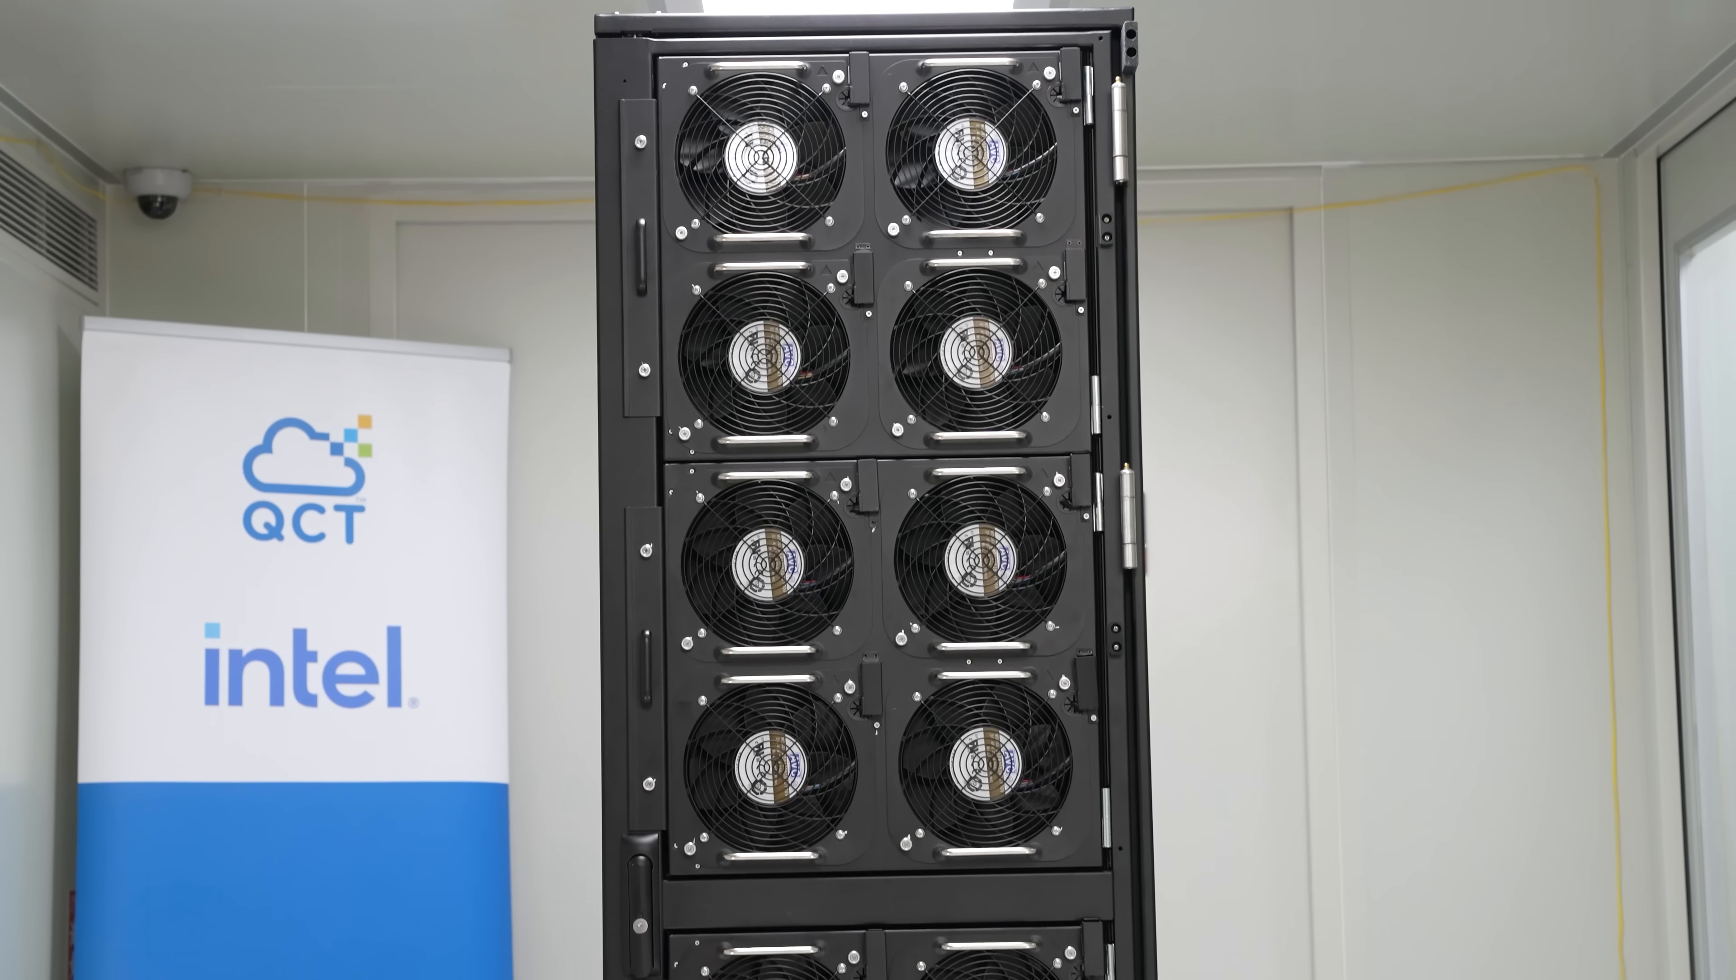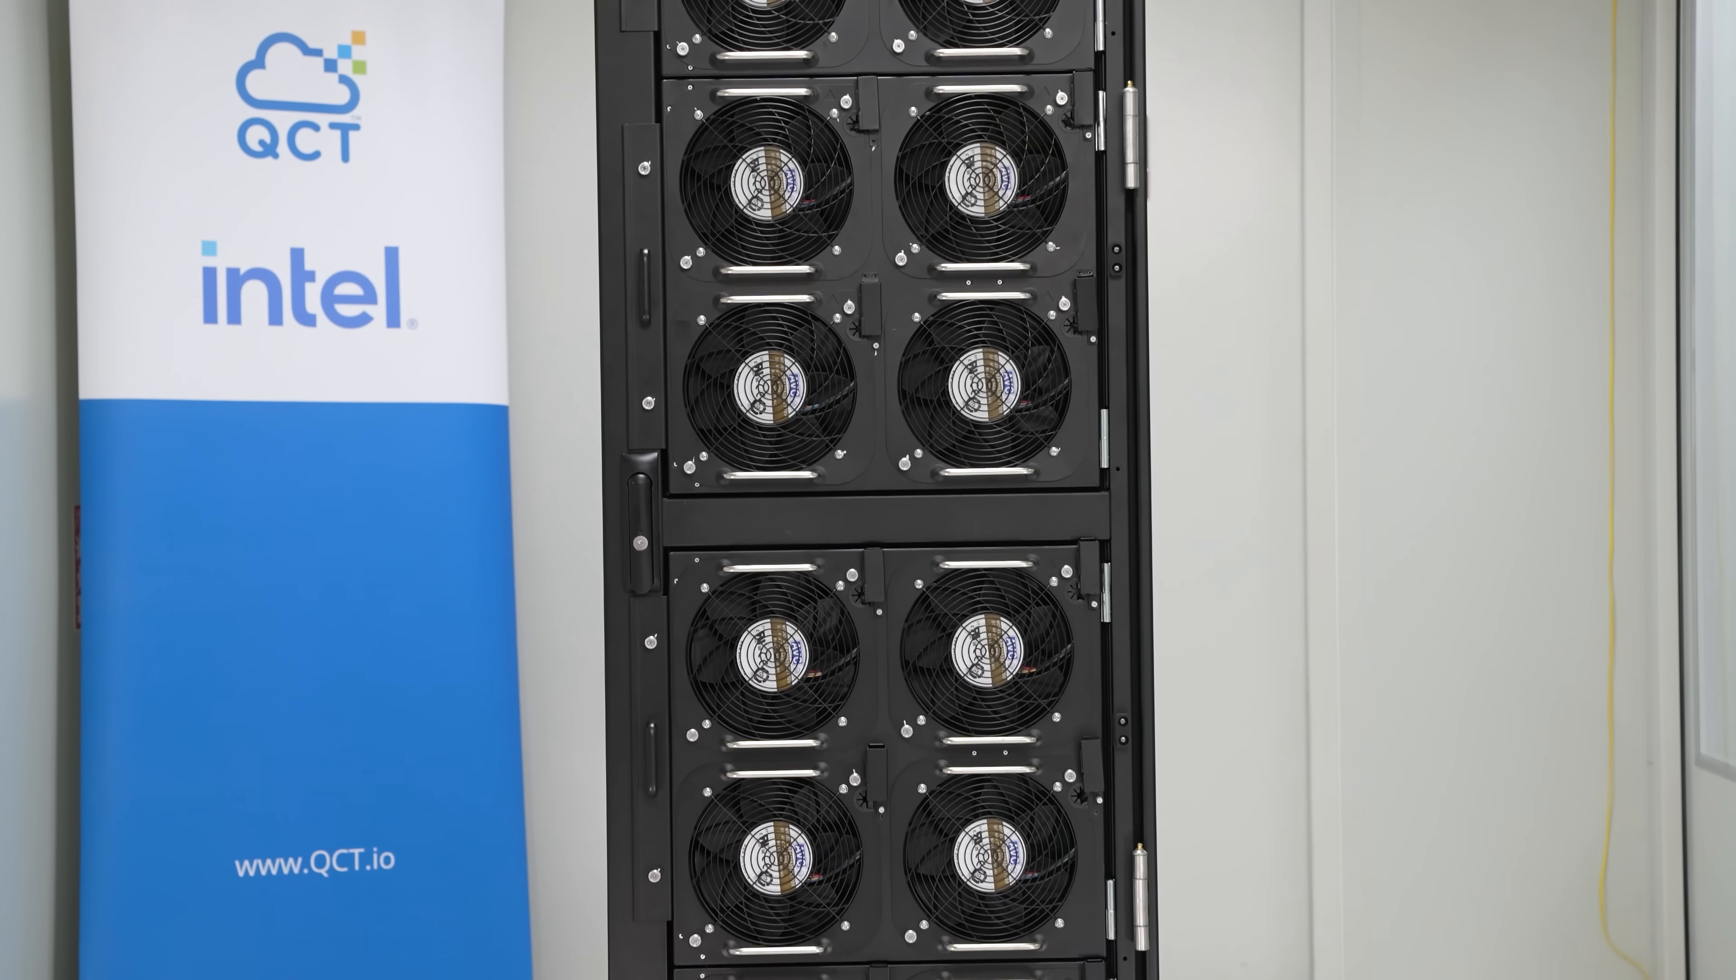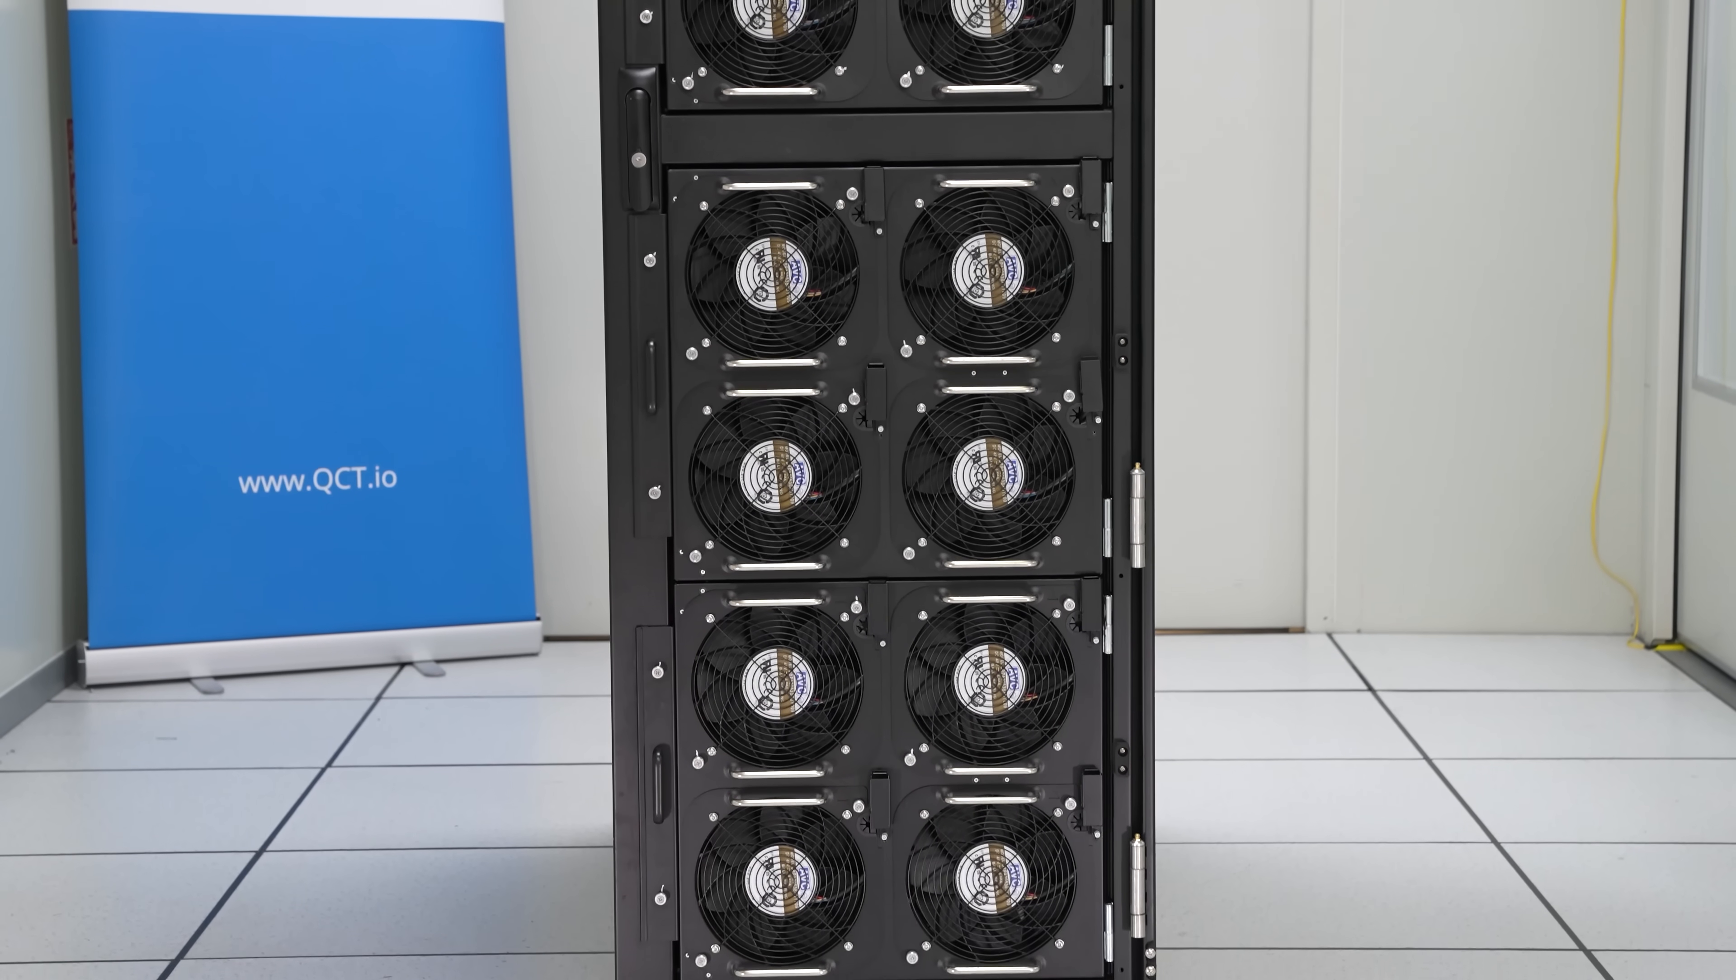You can also do things like end-of-aisle coolers or something like that, but the idea is that you're just kind of taking heat away from that rack. So that CDU has its own redundant power supplies, and you also have features like redundant pumps. They even let me go and pull one of the pumps, which was fun. And by the way, those pumps are actually pretty heavy. Now, of course, you can do things like use facility water, you can use end-of-aisle or something like that, CDUs and all that kind of stuff, but probably the more interesting one is what Quanta is using with the cool rack.